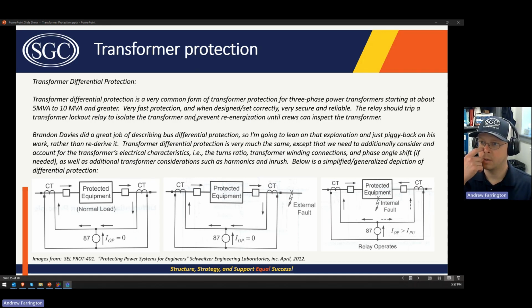So we left off, we were going to start on the actual transformer protection aspects of transformer protection. The most, I would say, important to understand piece of transformer protection is transformer differential protection. This is usually used for transformers that are 10 MVA or greater.